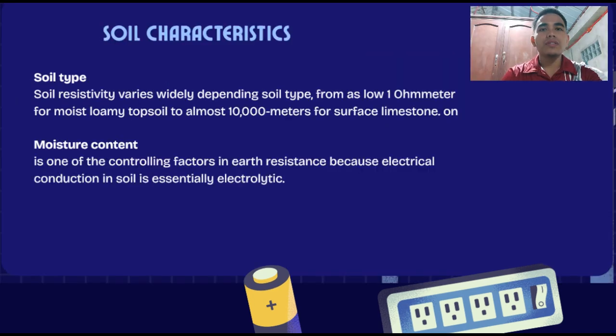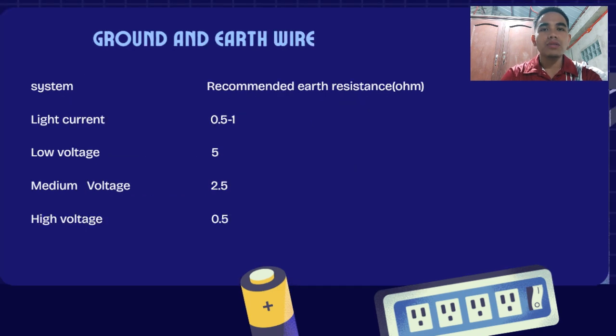So, soil characteristics. Soil type: soil resistivity varies widely depending on soil type, from as low as 1 ohm-meter for moist, loamy topsoil to almost 10,000 ohm-meters for surface limestone. Moisture content is one of the controlling factors in earth resistance because electrical conduction in soil is essentially electrolytic. So next is the ground and earth wire.